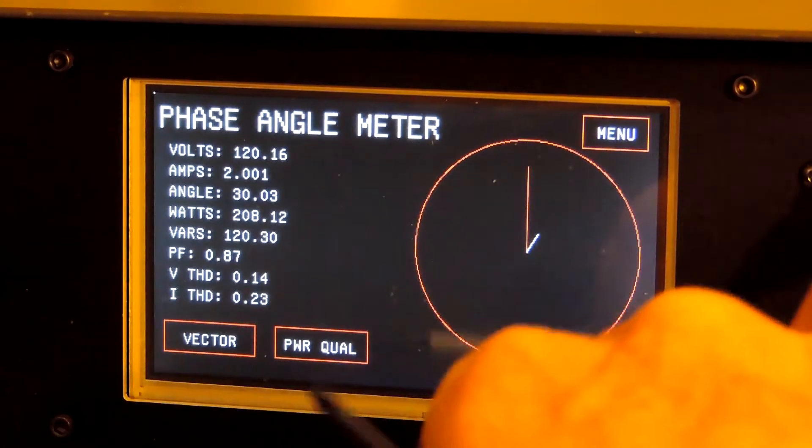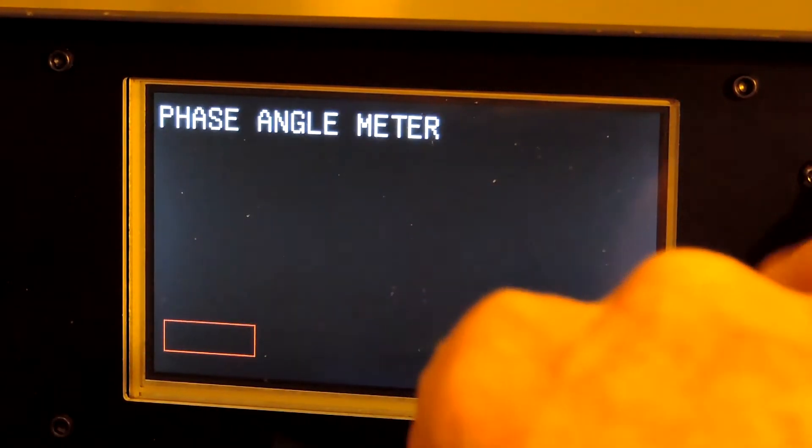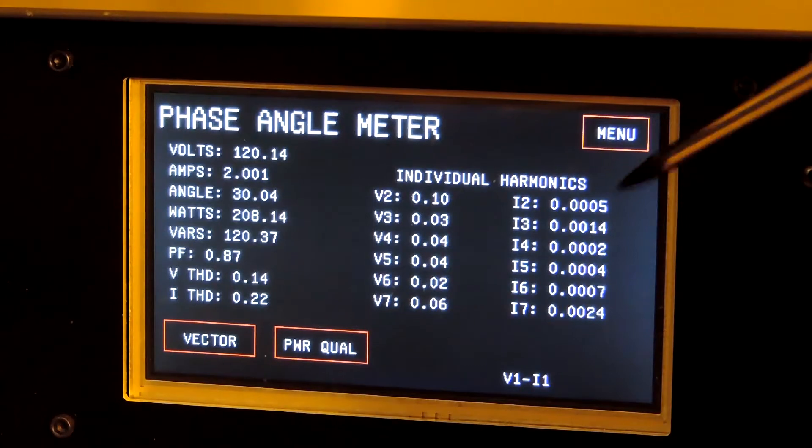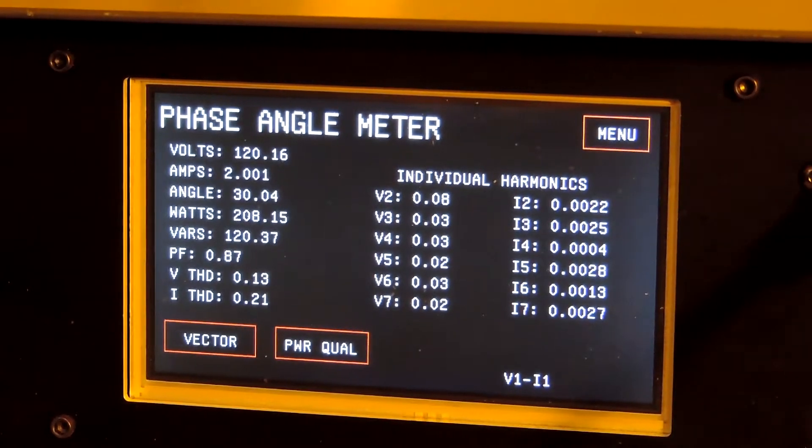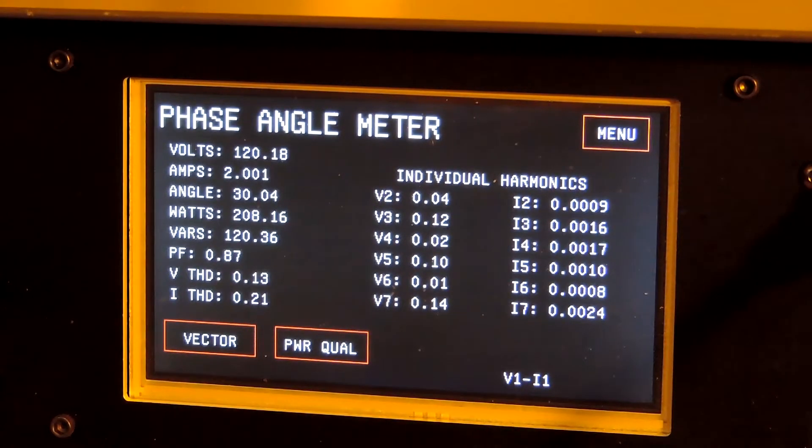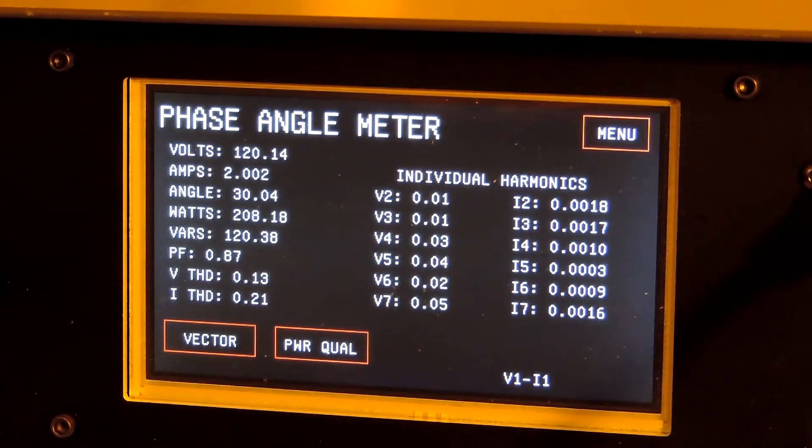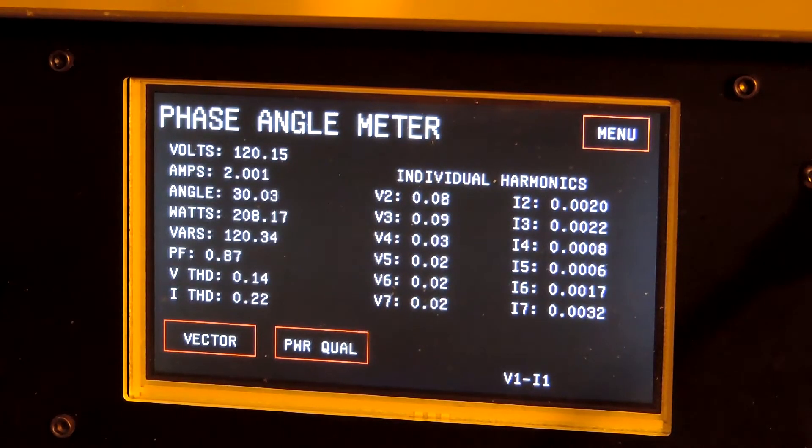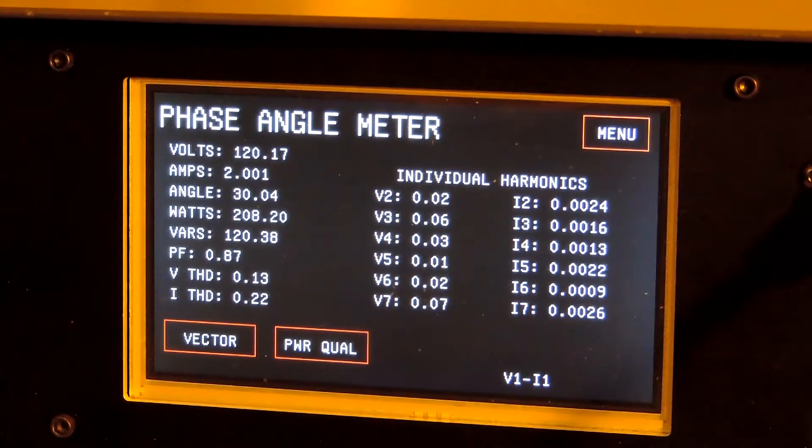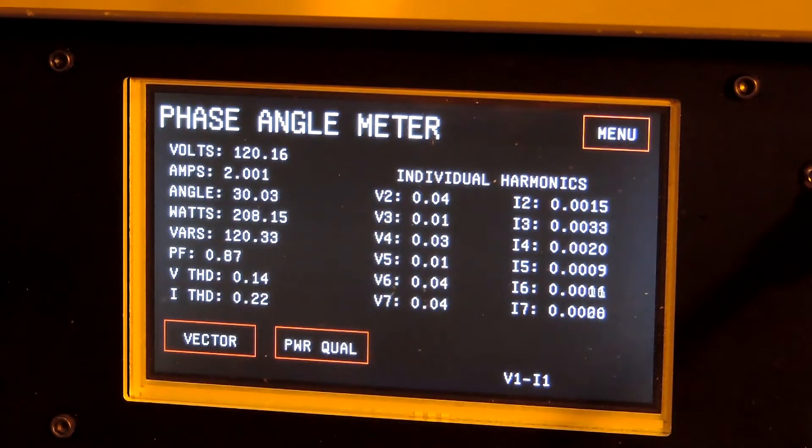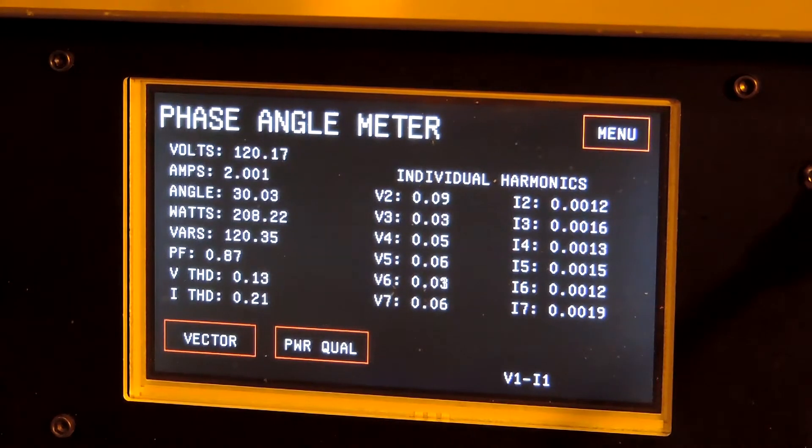If I touch power quality, you can see I have the individual harmonics over here, the second through the seventh. Right now the distortion is very low so they kind of roll, a little bit of aliasing rolling through there, but at one to three percent distortion it can be calibrated against the Keithley.